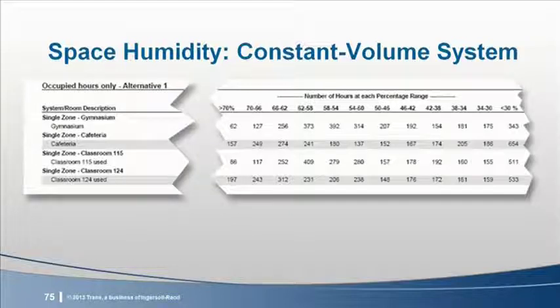A large quantity of hours on the left side would represent many occupied hours with high relative humidity. As a general rule of thumb, ASHRAE Standard 55 tells us that high relative humidity levels combined with low metabolic activity results in occupant discomfort. For the classrooms, these occupied hours of high relative humidity may be poor for the students and faculty.